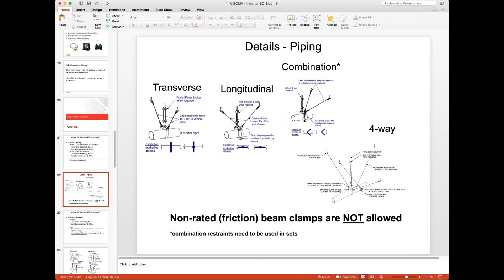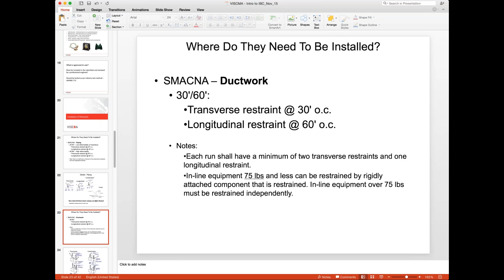Now, on ductwork, we use a different standard. We use a 3060. All elements of what we had done on the piping is the same. We go through the math, determine the load, determine the required capacity of the brace that we're going to apply. And the same thing, each run requires 2 transverse restraints and 1 longitudinal. And in the code, there are standards as to what defines a run. If it's a typical bend or such, some of it may be small enough where it is not a run. And then inline equipment, 75 pounds and less can be restrained when it's rigidly attached to the ductwork. Anything over it has to be independent. The assumption there is something weighing 75 pounds or less, the standard design and construction of the duct will restrain and support that 75-pound piece of equipment.